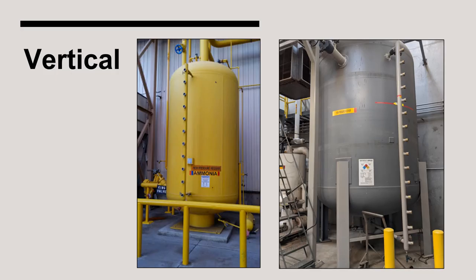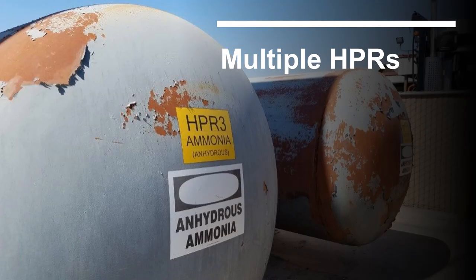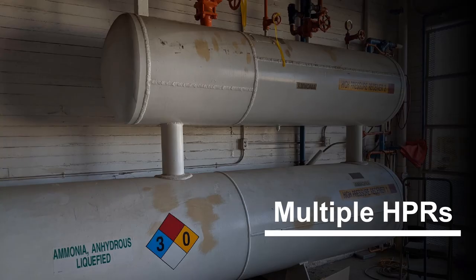High pressure receivers can also be vertically oriented. Vertical receivers offer the advantage of occupying less square footage, but a downside is that the valves on top of the vessel can be difficult to access. It is not uncommon for larger systems to have multiple high pressure receivers. When this is the case, the HPRs are typically interconnected so that they operate in concert with the same liquid level. The arrangement in this picture is quite unusual in that the two receivers are stacked on top of each other — a good reminder that no two systems are exactly the same.